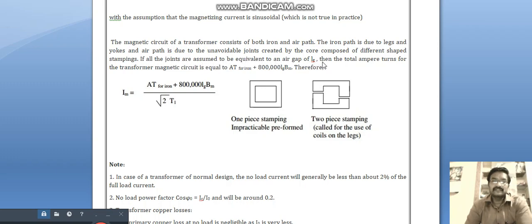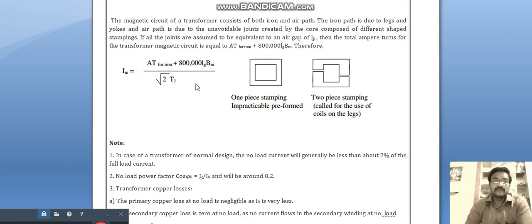If all the joints are assumed to be equivalent to an air gap of Lg, then the total ampere turns for the transformer magnetic circuit is equal to AT for iron plus 800,000 Lg Bm. The Im is equal to AT for iron plus 800,000 Lg Bm by root 2 T1.